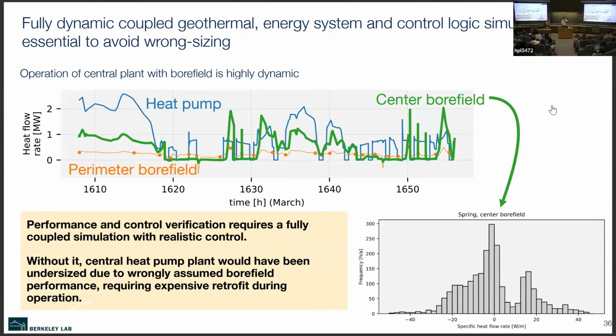If you look at the frequency diagram on the lower right-hand side, that shows for the spring, for the center bore field, heat extraction rates between -40 and +40 watts per meter. That was the initial value we used in the MILP optimization, suggested from the literature, but during operation we almost never get to that performance. So it was critical to learn from the detailed Modelica model what the actual performance is, put that back into MILP, and see what it does to the sizing of the equipment and the whole techno-economic optimization.